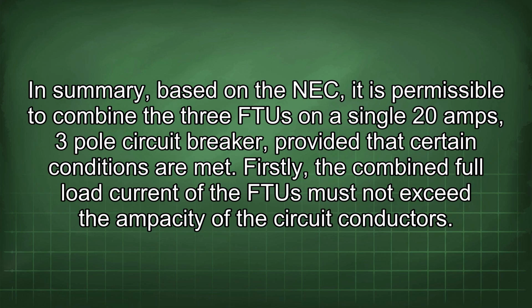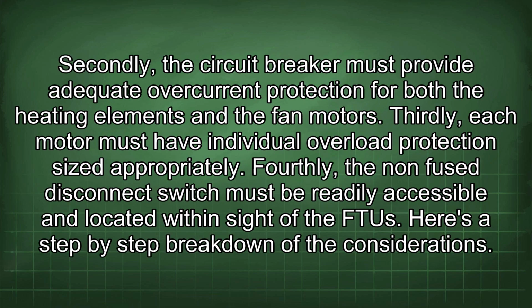3-pole circuit breaker, provided that certain conditions are met. Firstly, the combined full load current of the FTUs must not exceed the ampacity of the circuit conductors. Secondly, the circuit breaker must provide adequate overcurrent protection for both the heating elements and the fan motors.